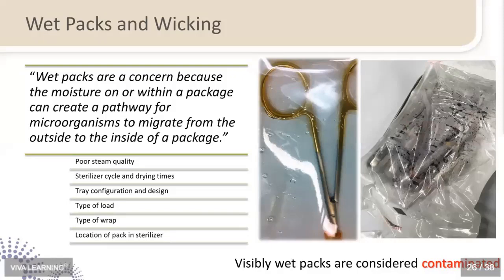And wet packs are in fact a concern, because if the fabric, whether it's the crepe of the wrap or the paper of the pouch, is still damp, if it is not bone dry, it means those pores are still open. And you have a chance of wicking bacteria from either your hand, your glove, the countertop, whatever, into that package. So wet packs should never be touched. And you can't take them out and say, I'll just let them dry on the counter. That's what your dry cycle and your sterilizer is for. You cannot use fans on damp packs to dry them. That is off-label use of a medical device.